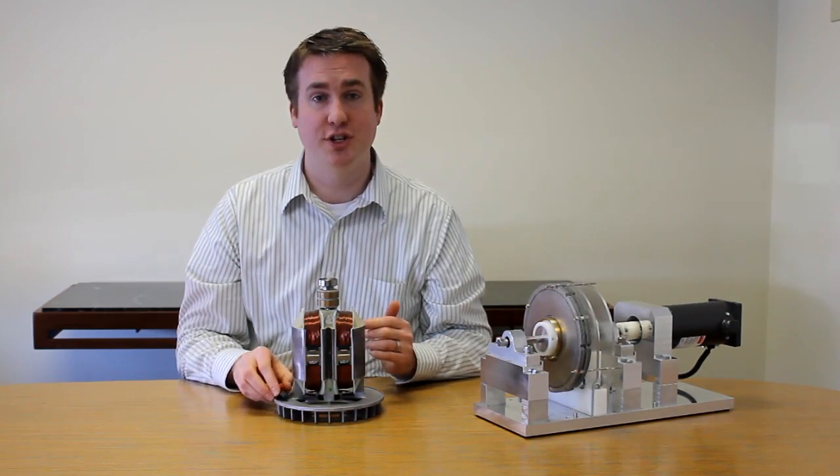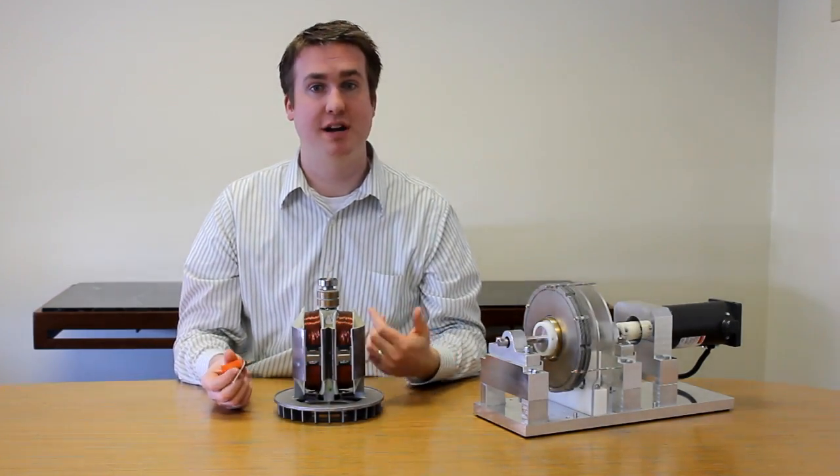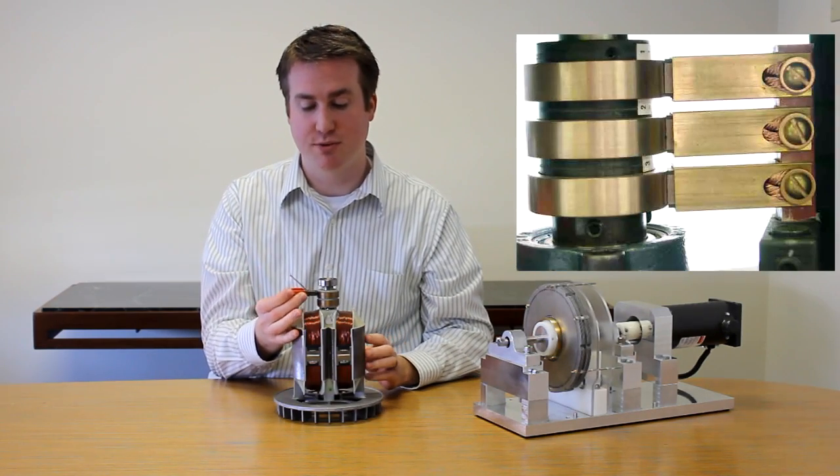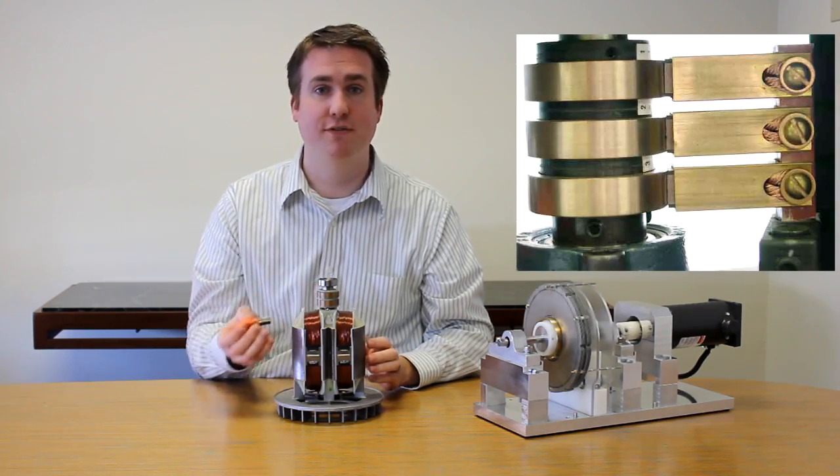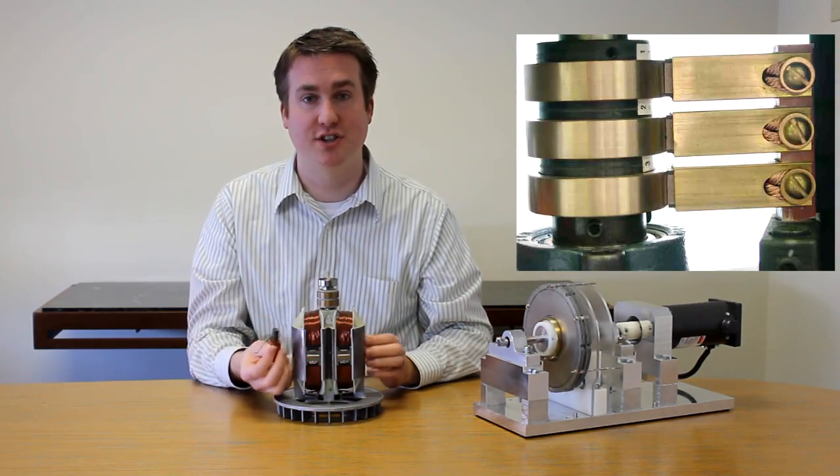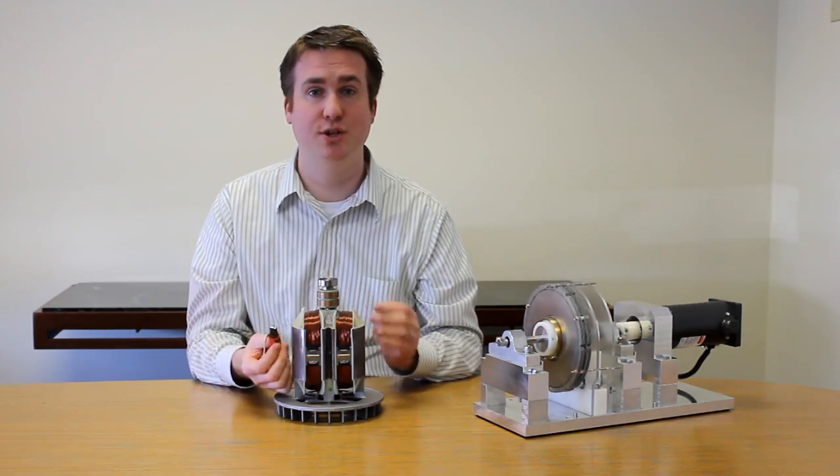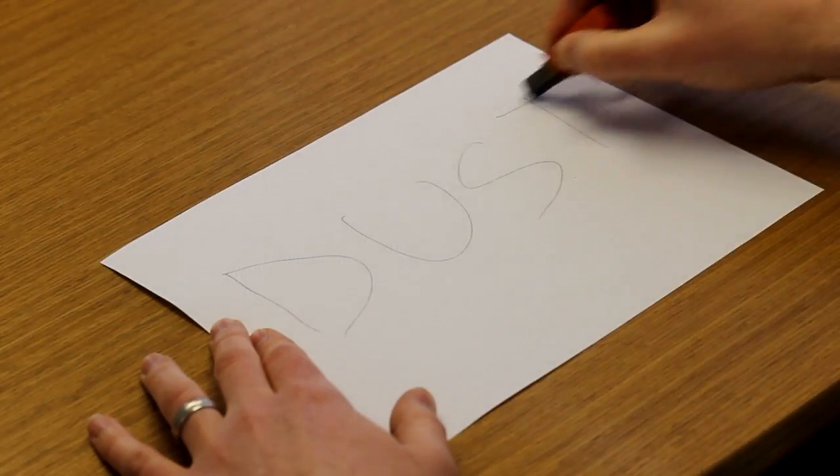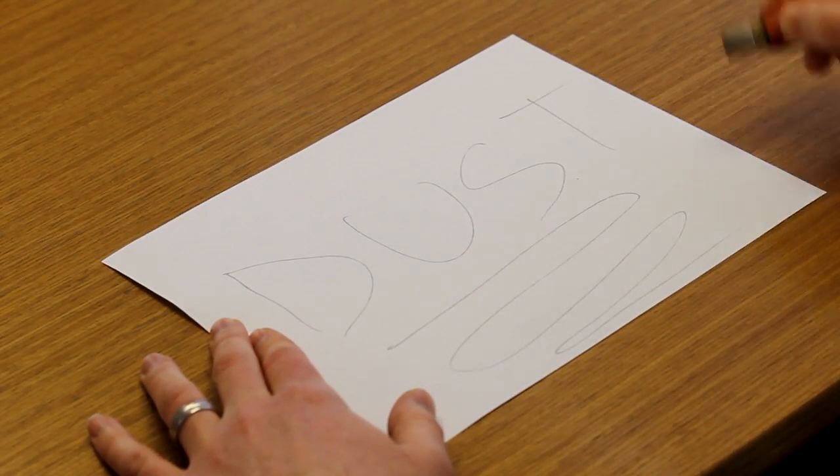The earliest solution to powering electrical components that rotate used carbon brushes in contact with rings on the shaft. Unfortunately, the sliding connection causes both the brushes and the rings to wear over time, requiring periodic maintenance to clean brush dust and replace worn parts.